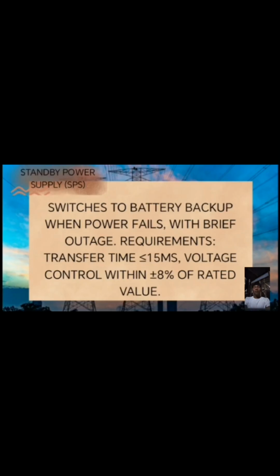So, the standby power system or SPS switches to battery backup when the main power fails, usually with a brief outage. It requires a transfer time of 15 ms or less and voltage control within plus or minus 8% of the rated value to ensure proper operation.